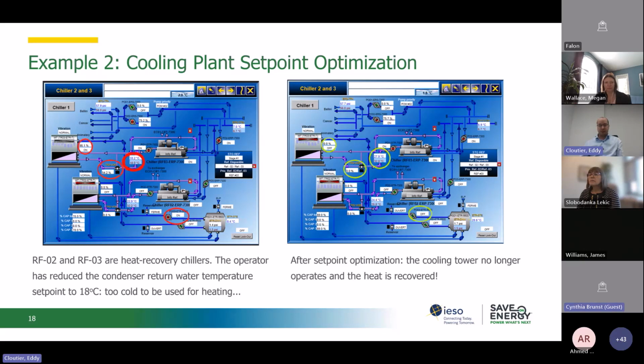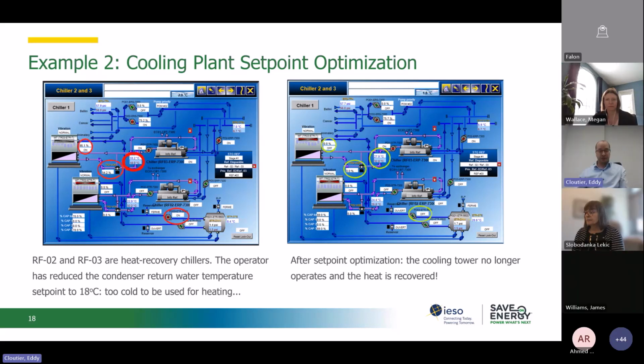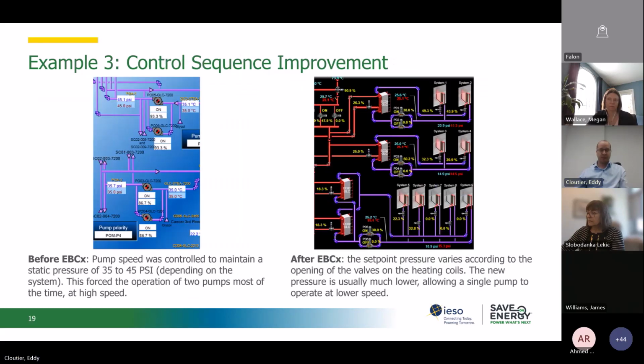In this case, we have rectified the set point and better trained the operators in understanding their system. As we can see on the right, for the same outside air temperature, all the energy is recovered and there is no longer any discharge at the cooling tower. So this is a second example.